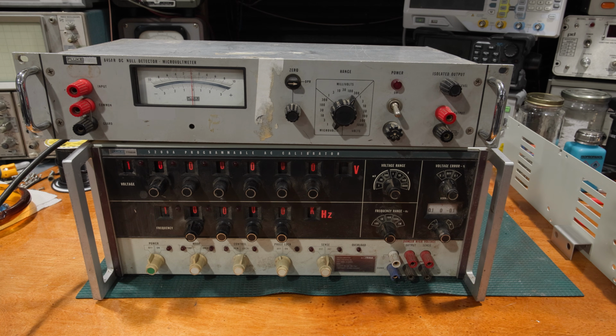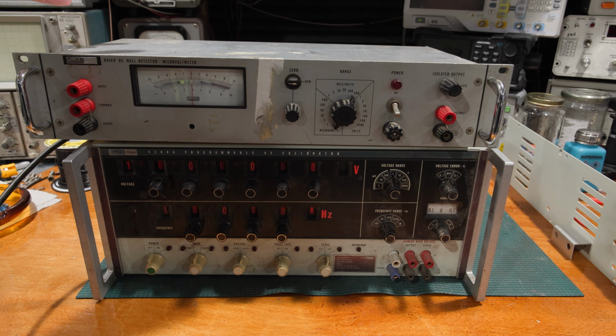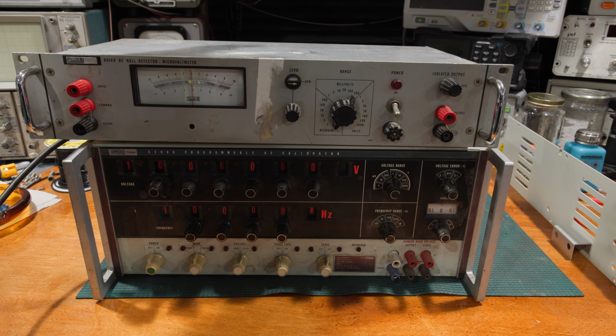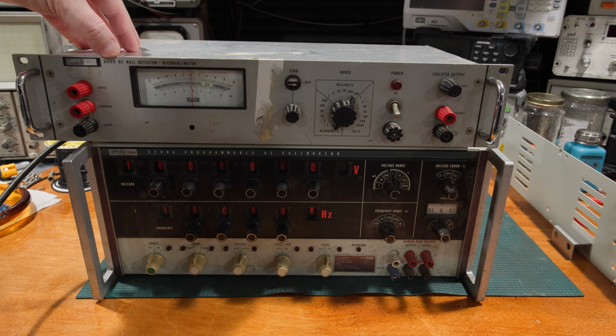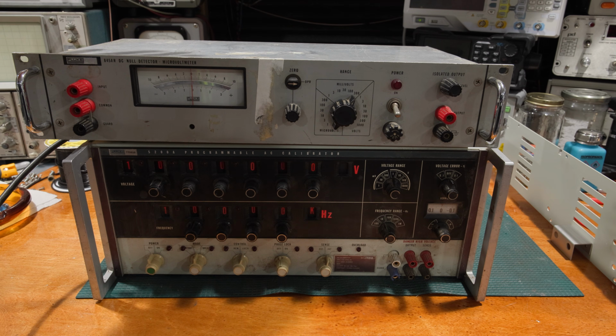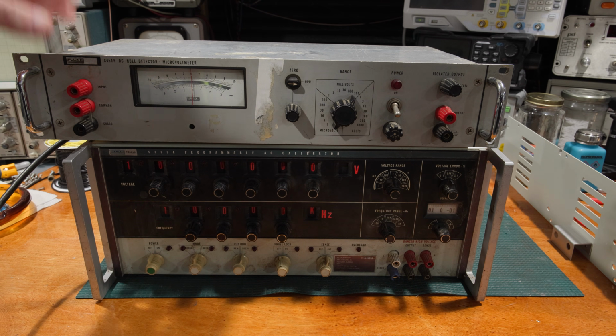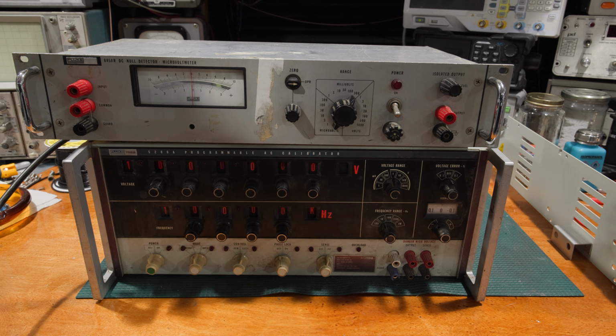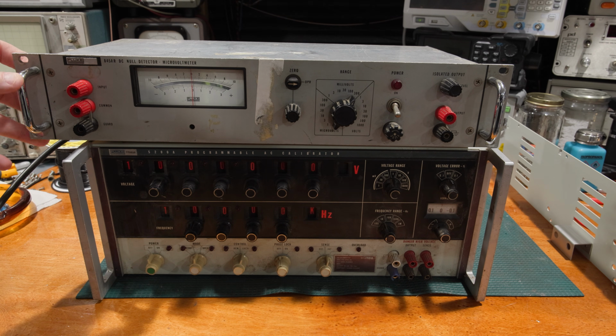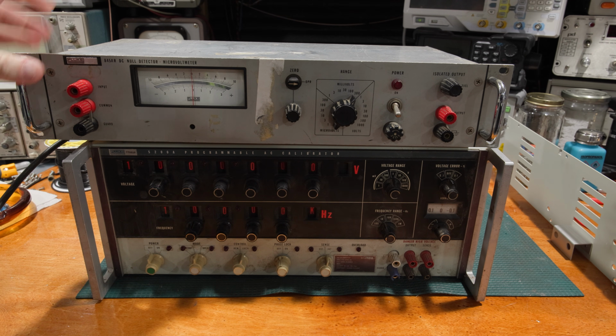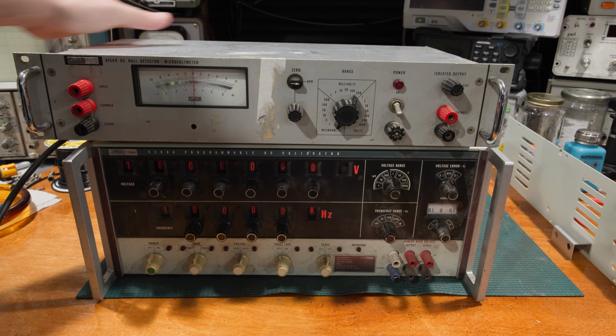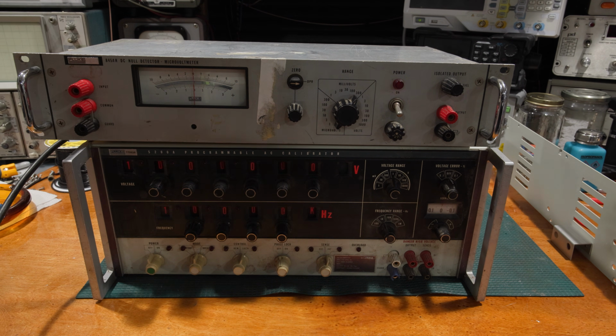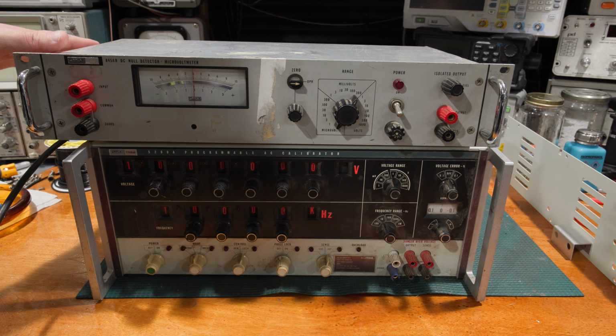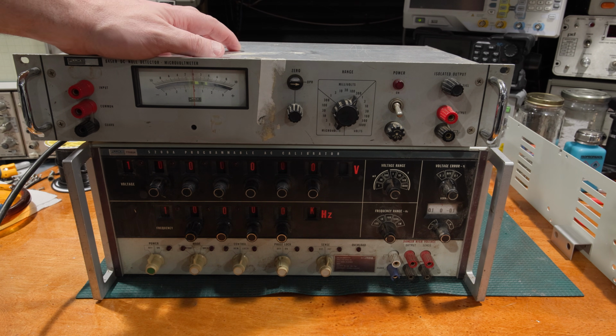So I needed a null meter. Enter this thing, which is a Fluke 845AR as opposed to the AB. You're gonna see some rack gear come into the channel, and that's kind of foreshadowing to some future plans. I liked this unit for two reasons. One, it was rack mount. It's very, very light, solid because of the 1 microvolt range. This thing is completely solidly shielded, no air holes, no nothing.